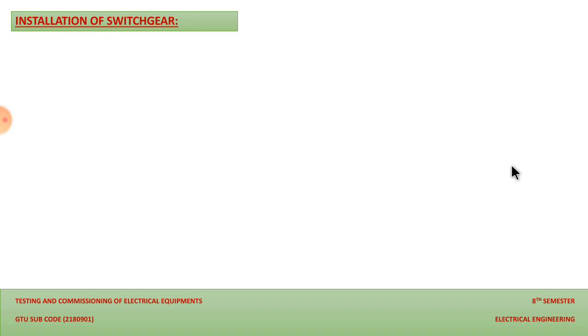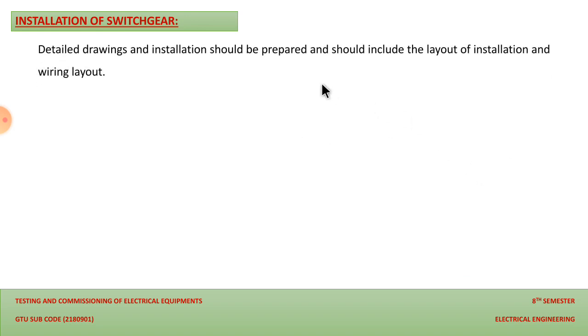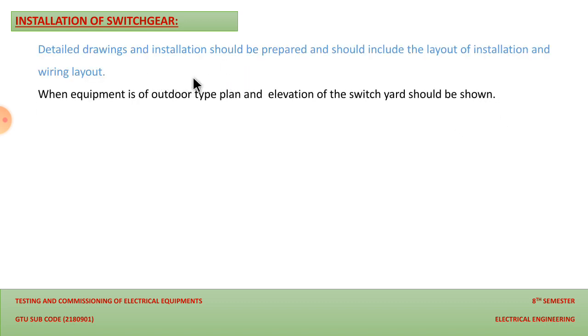Then the next is the installation of the switchgear. How the installation of the switchgear is carried out, we are going to discuss through this slide. Detailed drawings for installation should be prepared, and they must be provided by the manufacturer or the company. They should include the layout of installation and the wiring layout. This will be helpful for future maintenance also. If the layout is there, then the person can do maintenance with proper guidance. So this is necessary. The drawing and other amenities related to the installation must be provided by the manufacturer or company.